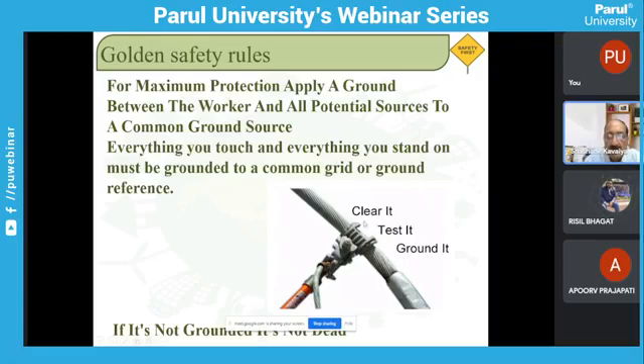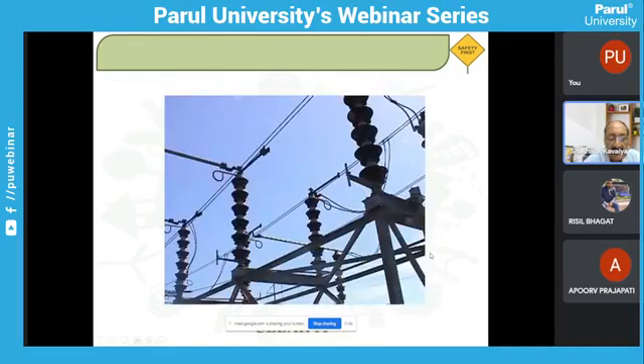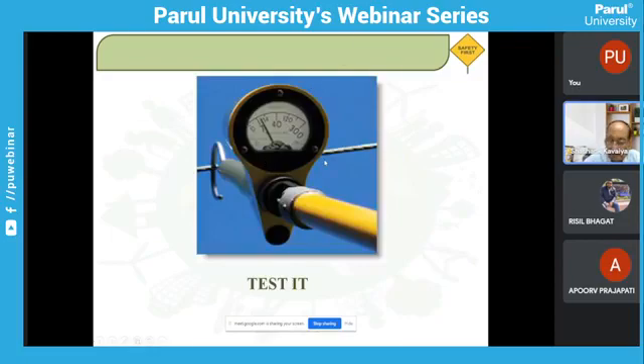So let power be clear. Test it. Once isolated, test it and ground it. Again, the isolator you have to make sure is open, then test it to confirm there is no voltage.